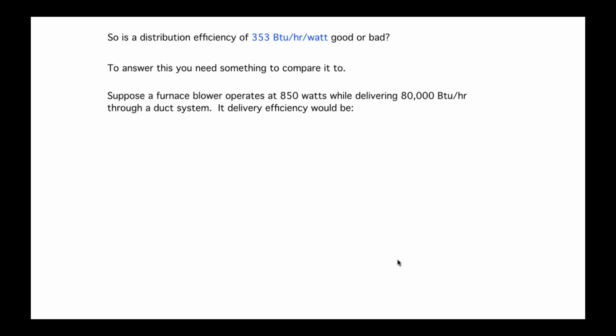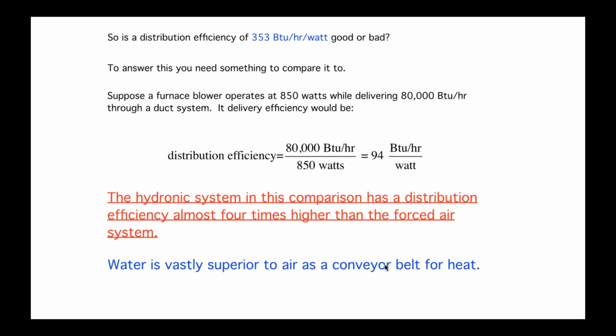But let's say we've got a furnace that delivers 80,000 BTUs per hour, and that blower is requiring 850 watts to make that delivery. So again, we just do a ratio. 80,000 BTUs per hour divided by 850 watts, we're at 94 BTUs delivered from where it's created to where it's needed per watt. And you can see in this comparison, and these are just two specific systems here, the hydronic system is almost 4 times more efficient, or we could say the hydronic system is delivering the same amount of heat using almost 1/4 of the power required by the forced air system.